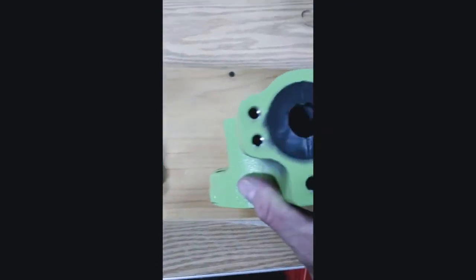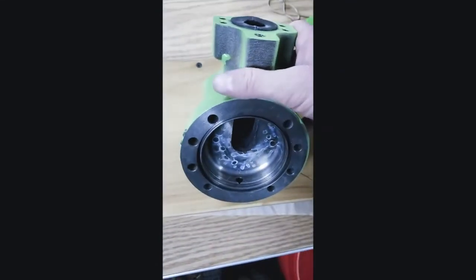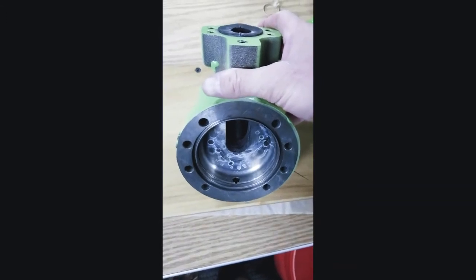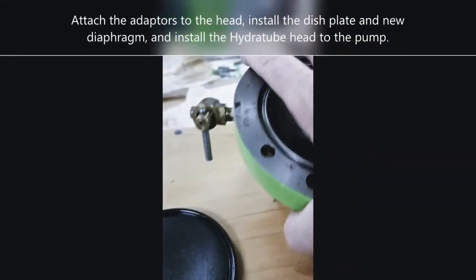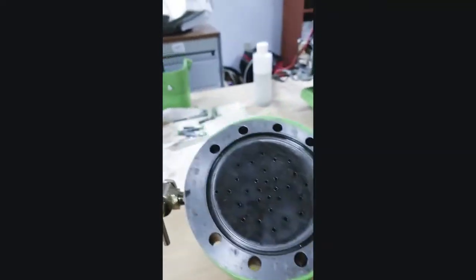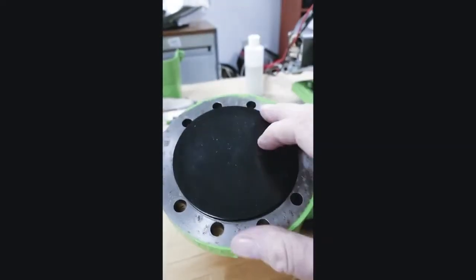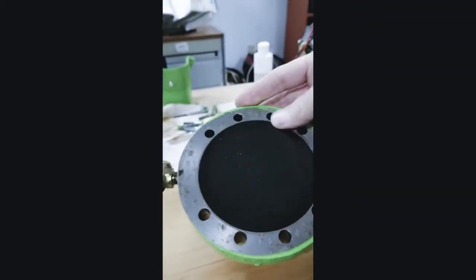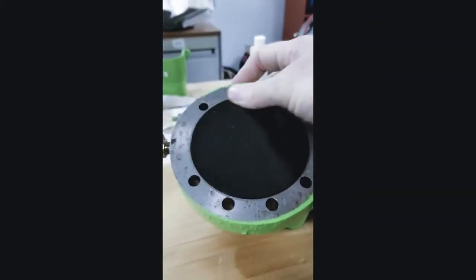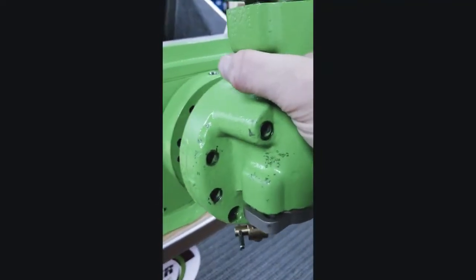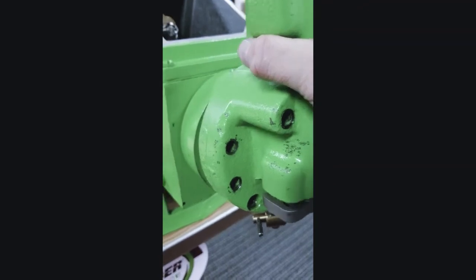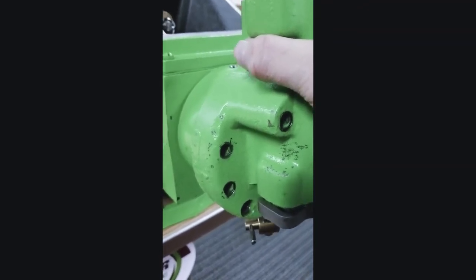And now I'm ready to put my adapters back on and tighten those down. I'll put my dish plate back in, and I'll mount this back onto the pump head. Okay, so I've put my adapters back on and screwed them down, and I've got my dish plate installed now. So my last step with the Hydratube head is to install a brand new diaphragm. And with that installed, I'm now ready to mount that onto my pump and prepare to prime this thing and get it running.